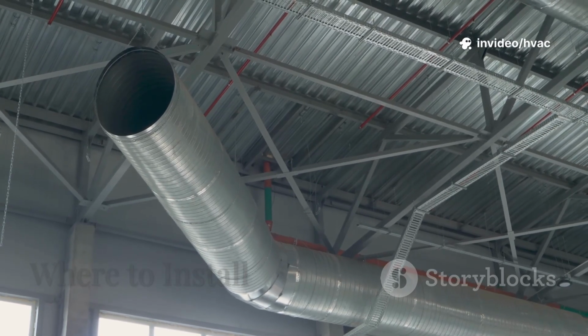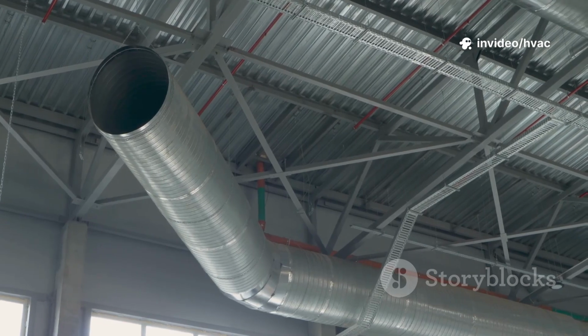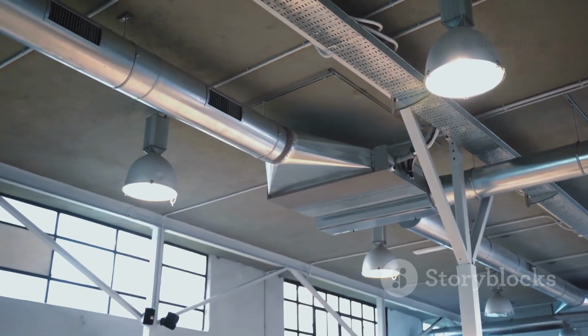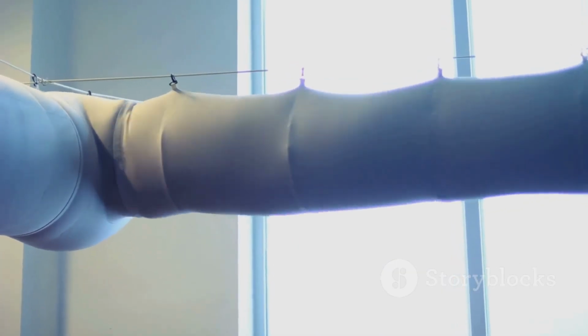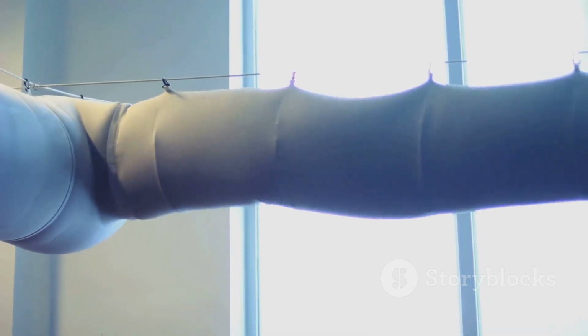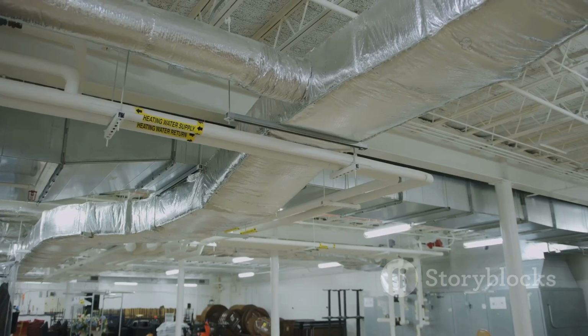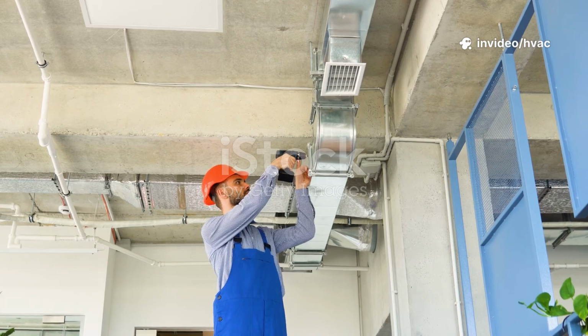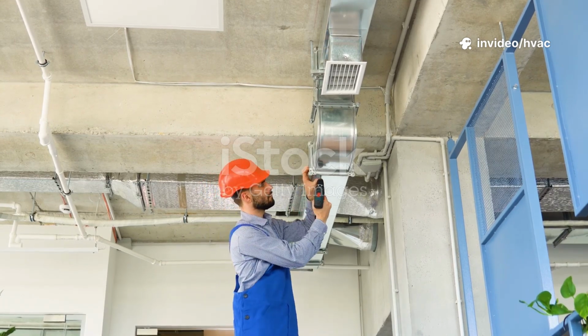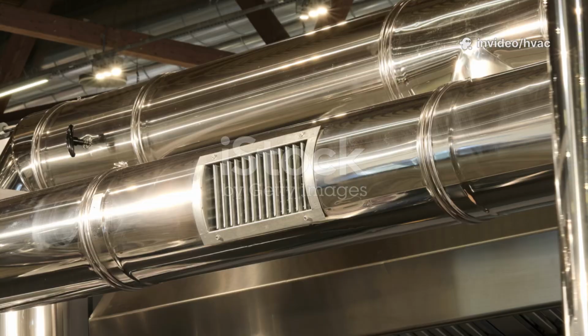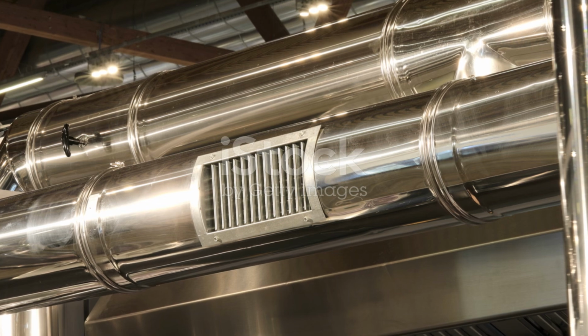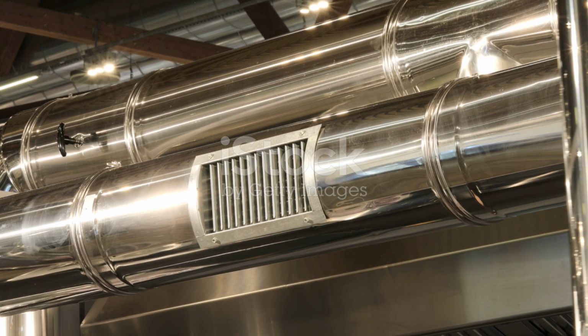You should always install an airflow measurement system on a straight section of duct where the airflow is nice and uniform. It's important to avoid spots right after bends, dampers, or branches, since those can mess with your readings. And don't forget to follow the manufacturer's recommended clearances both upstream and downstream. Usually you're looking at about 5 to 10 duct diameters for the best accuracy.